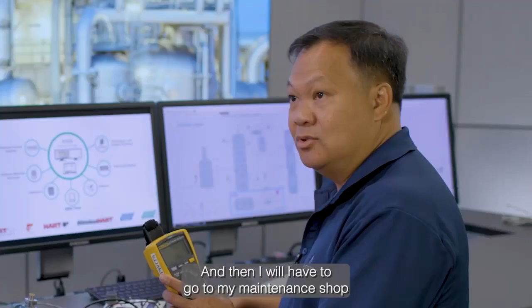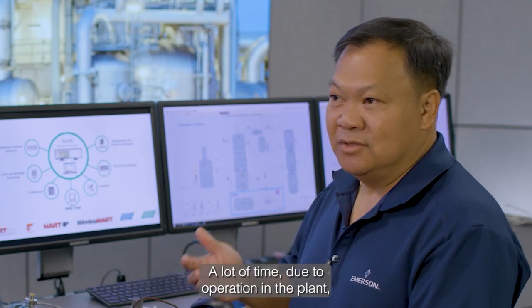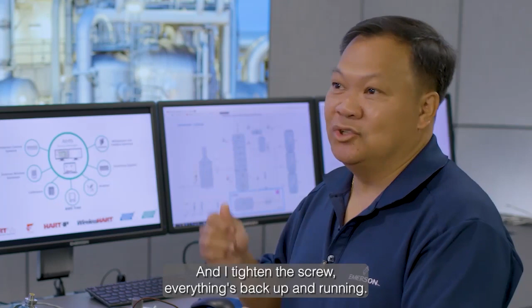Once I go to the field and open up the panels, I make sure there's power to it, and that there's proper amperage so the drive is good. Then I hook my field communicator to it, and it's not reading. I say, what's going on? I've got all the stuff I need. So I check to make sure it's not a loose wire—a lot of times, due to vibration in the plant, things come loose, and typically that's it. I tighten the screw, and everything's back up and running.